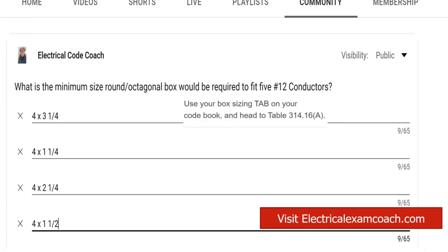For this, we're going to use our box sizing tab. If you've used the Mike Holt tabs as prescribed for your code book, you're going to head to table 314.16(a). I like to look for the box first to make sure I'm in the right section of the table. I start on the left-hand side, go down, and find the type of box — in this case, the round octagonal box, which is right at the top. Then I slide over to the gauge conductor I'm working with, which is 12, then slide up to find the smallest box that will carry all these conductors. In this case, it's a four-inch by one-and-a-quarter-inch box.